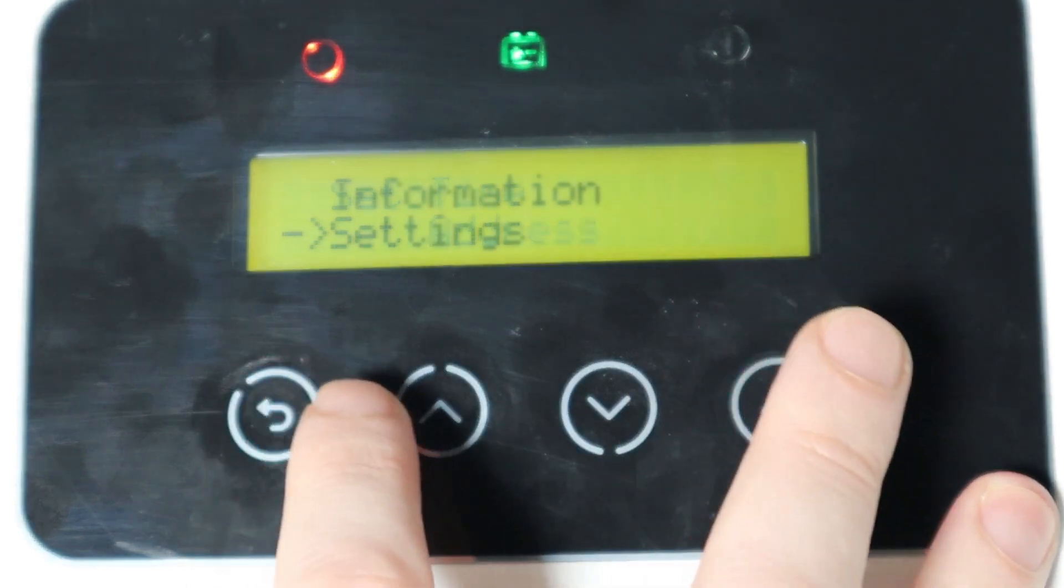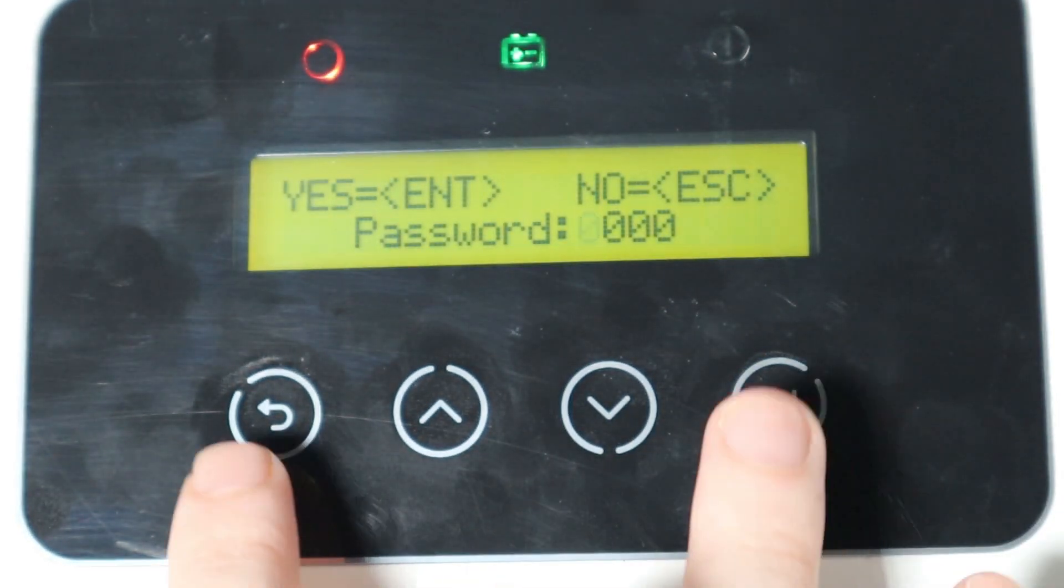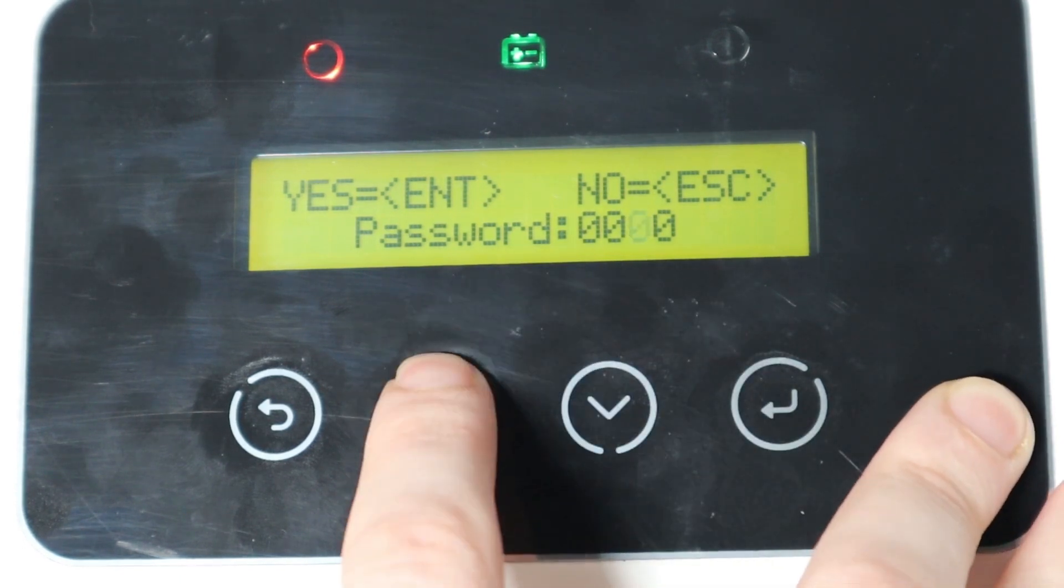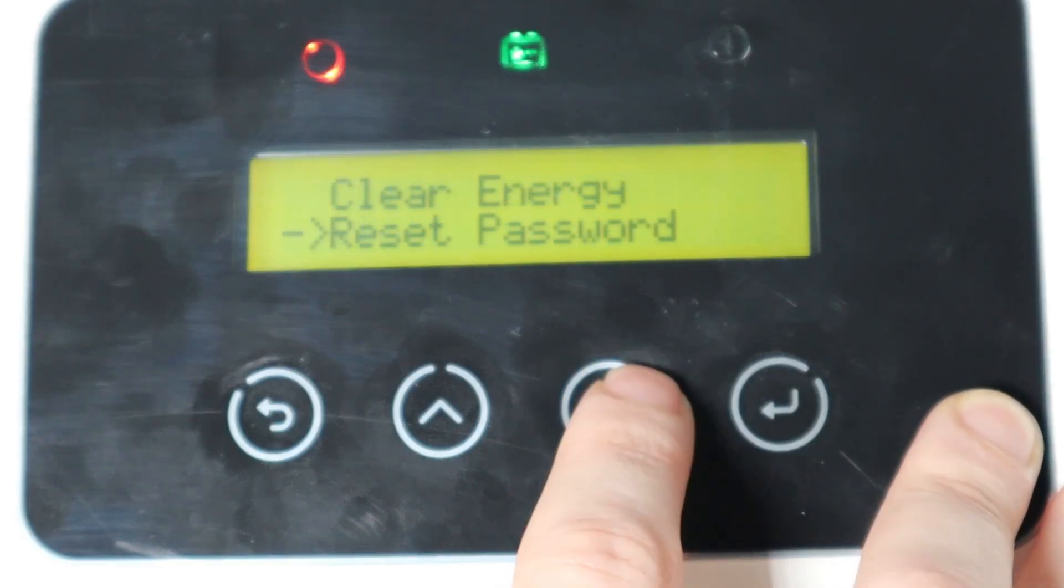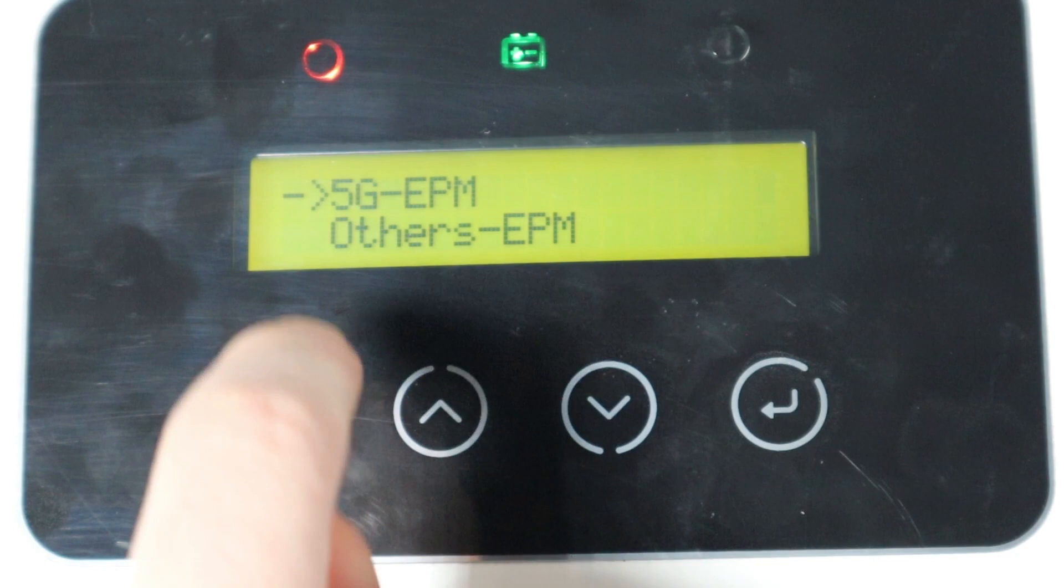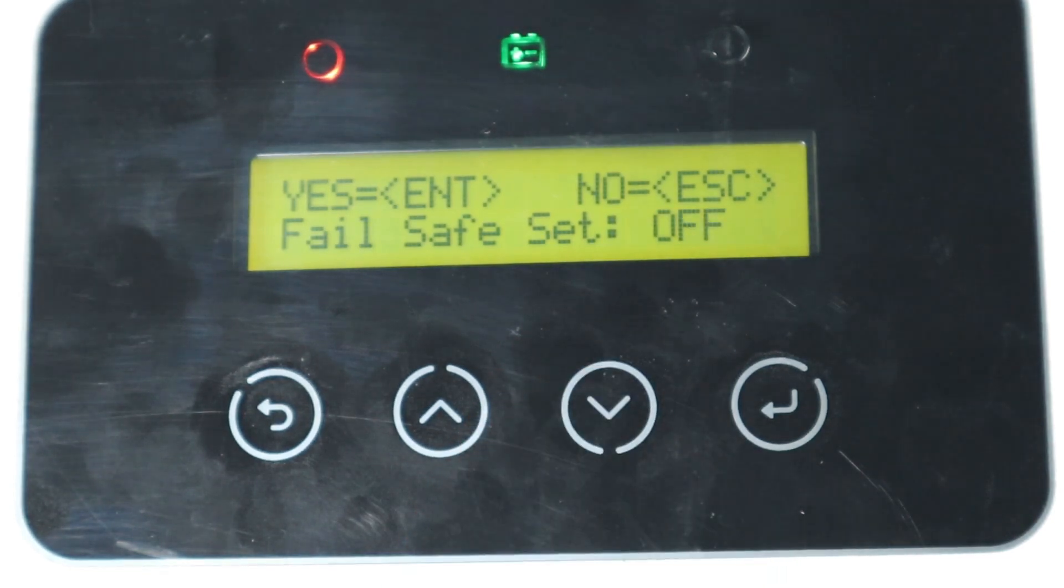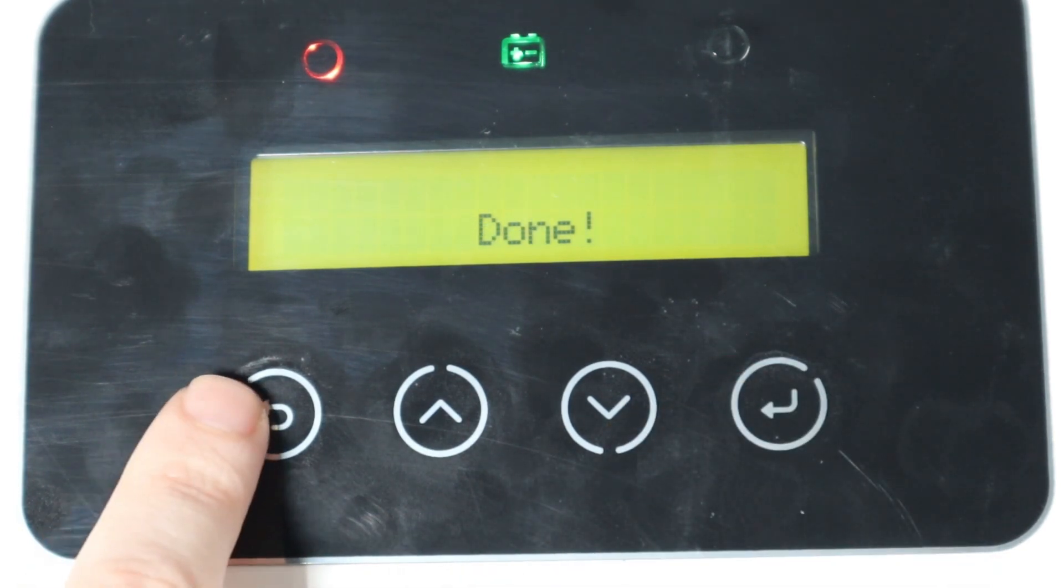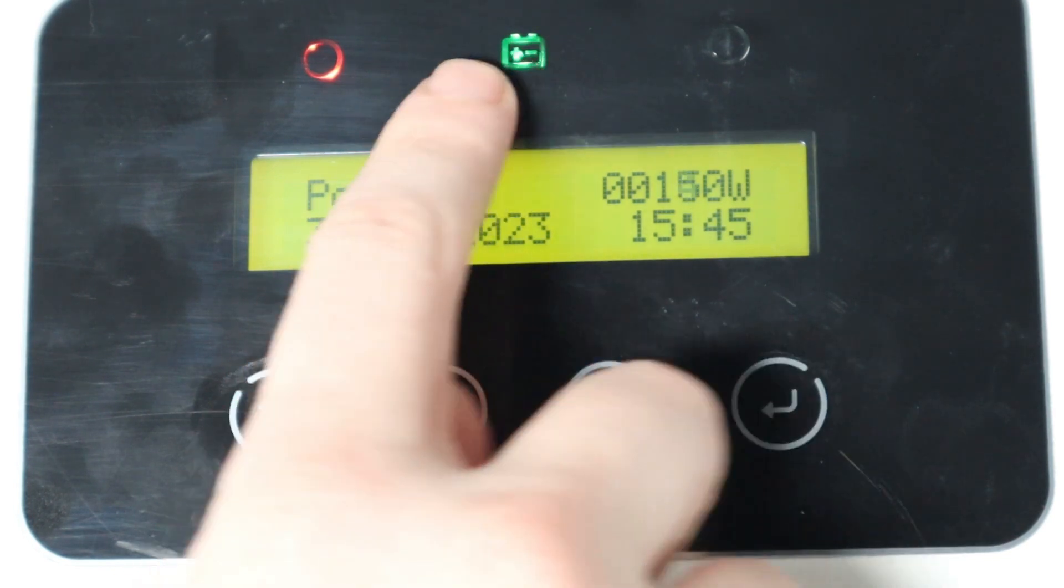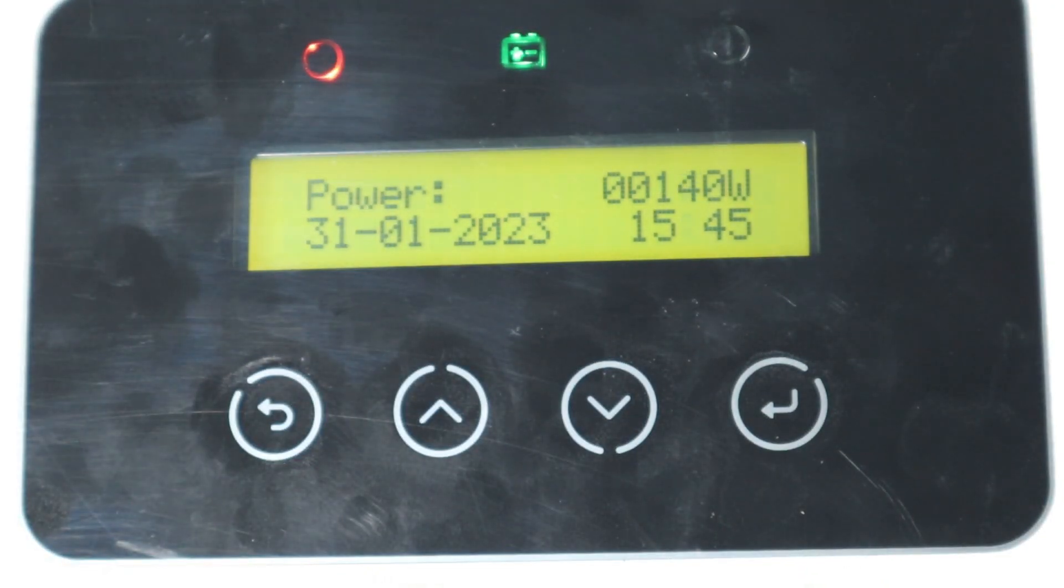Then the other thing we need to do is go to advanced settings. So go to advanced settings menu, press enter. On this inverter to wake it up, you press and hold these two buttons for five seconds. You type in the code, which is 10, like all our products. So you press down to move the cursor across, press up, press enter. Then you scroll through until you see external EPM set. Okay, so we go to external EPM set, press enter. This is a 5G EPM. So we press enter on that. And then we have failsafe already on. And by default, it is actually set to off. But you would need to enable that, and you press enter. If you had any communication issues, this will make it that the inverter stops generating as soon as you press enter. So if you get an alarm status as you enable that, it's because your communications is not set up, or your addressing is not set up correctly.